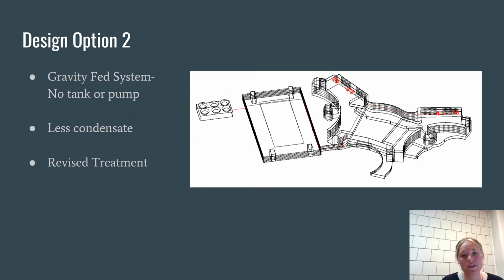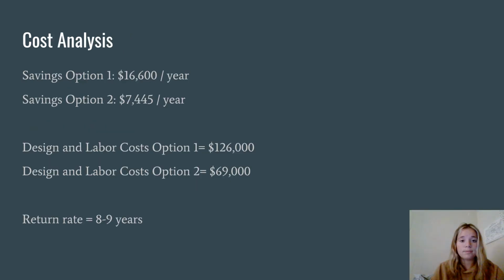For our alternative design, we will not be including the air handling units in the basement. Because of this, it's going to be a gravity-fed system with no tank or pump required. We're going to have less condensate, so the flow rate is going to be reduced to about 45 gallons per minute. And with this, we're going to have a revised treatment system that's scaled down to handle lower condensate flow rates.